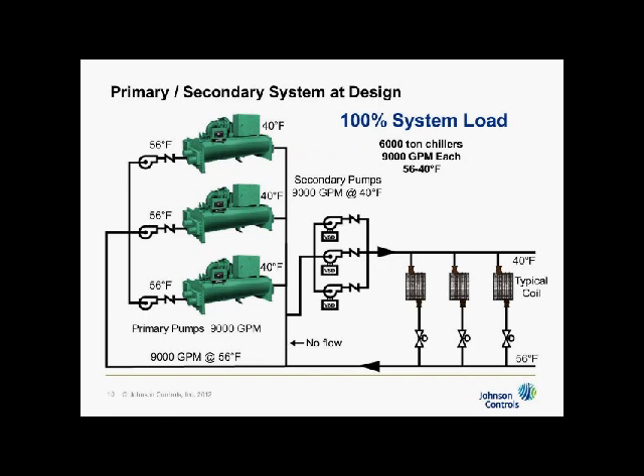If we look at a design of a system and we attach some numbers to it, we're going to look at 3 2,000-ton chillers doing 56 to 40 degrees for 9,000 GPM in the primary, and we also have 3 secondary pumps for which we're looking at 9,000 GPM in the secondary. In the secondary, we know that our delta T is going to be from 40 to 56. It's going to remain constant. And over in the primary, the flow is going to remain constant, and delta T is going to vary. So at 100% load, this is what I look like.